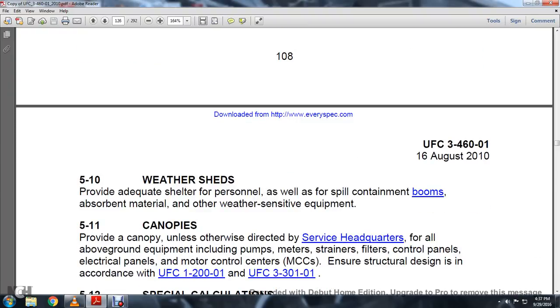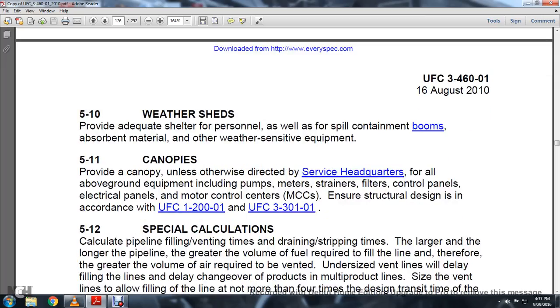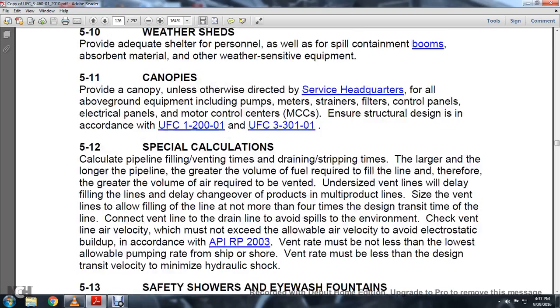510 weather sheds. Provide adequate shelter for the personnel, as well as spill containment booms, absorbent materials, and other weather-sensitive equipment. 511 canopies. Whenever provided, provide a canopy, unless otherwise directed by Service Headquarters, for all above-ground equipment, including pumps, meters, strainers, filters, control panels, electrical panels, and motor control centers. Ensure the structural design is in accordance with UFC 1-200-01 and UFC 3-301-01.